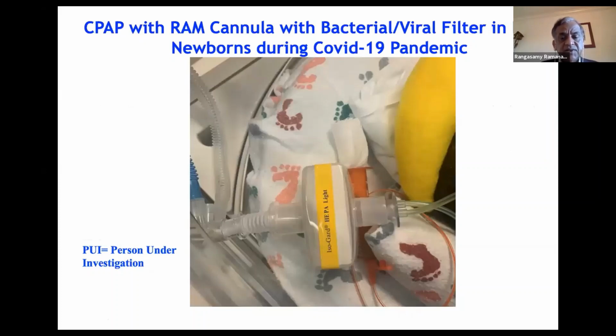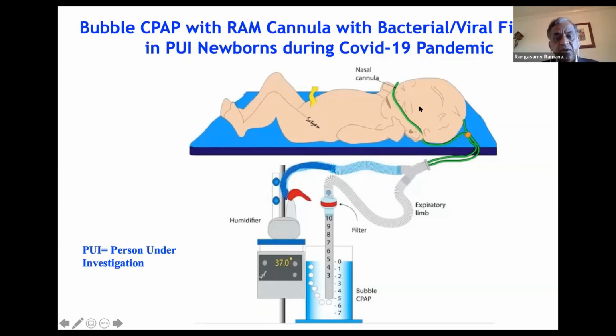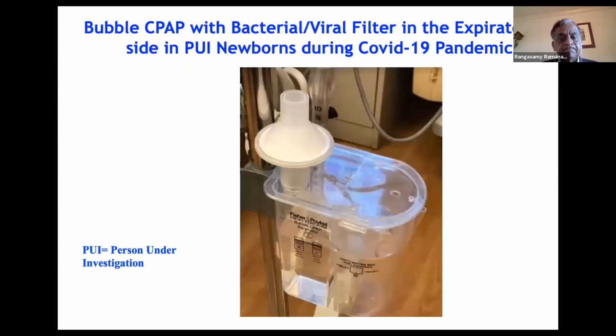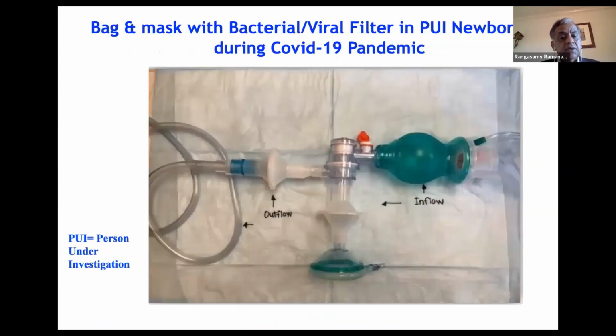Some COVID-related things, I showed you a little bit. Use a viral filter if you're ventilating babies, between the ventilator circuit and the RAM cannula or the prong or mask. If you're using bubble CPAP, we recommend a filter on the tubing that goes into the water column. Here is the setup where you put the filter on the water column. If you're bagging the baby, this is the gas inlet, the pressure control here, or a disposable pressure manometer here. This is the mask. You put a filter here.